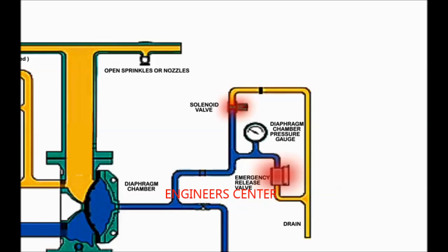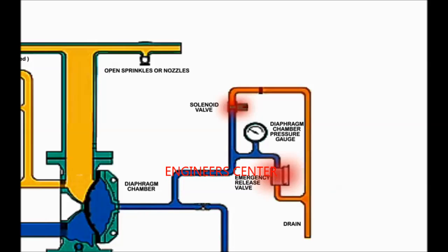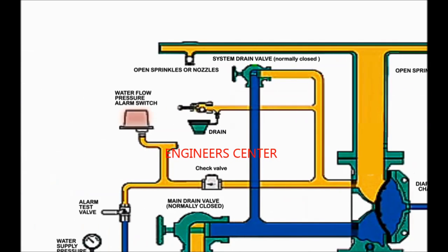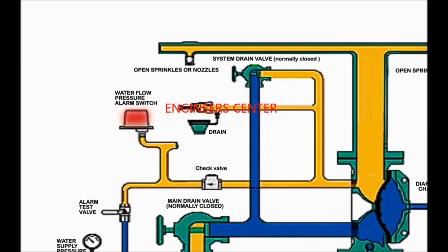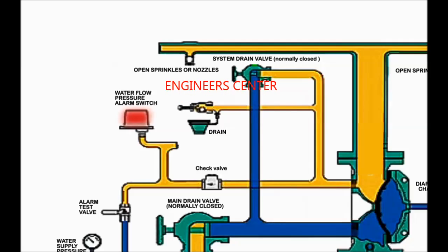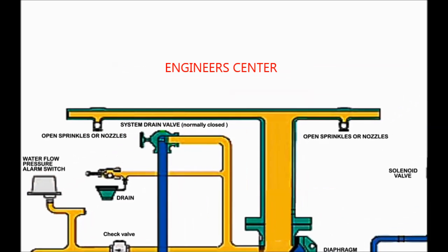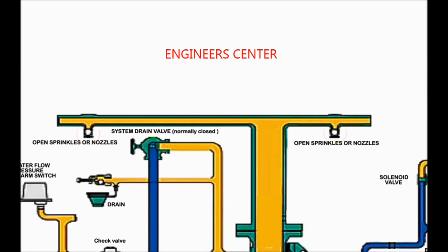Also present on the priming loop is the emergency release valve, which can be operated manually to activate the deluge system. The emergency release valve and the solenoid valve are connected from one end with the priming water pressure and connected to the drain — open to the atmosphere — from the other end. Here is the high pressure switch that is present on the outlet of the deluge valve, which gives an alarm signal in case of sensing supply water pressure. This alarm signal serves as an indication for activating the deluge system and may trigger actions according to the fire and gas system. Here is the outlet of the deluge system that is connected to the sprinklers or nozzles.